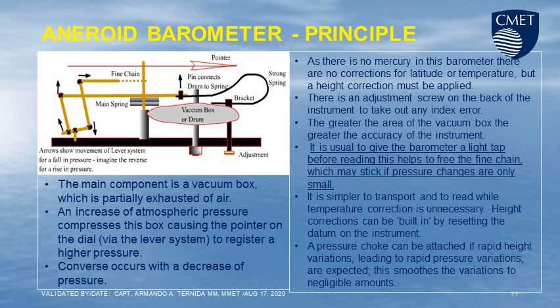The main component of the aneroid barometer is a vacuum box, which is partially exhausted of air. An increase of atmospheric pressure compresses this box, causing the pointer on the dial via the lever system to register a higher pressure. The converse occurs with a decrease of pressure. As there is no mercury in this barometer, there are no corrections for latitude or temperature, but a height correction must be applied. There is an adjustment screw on the back of the instrument to take out any index error.